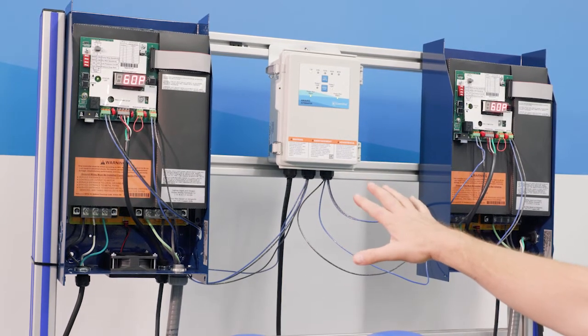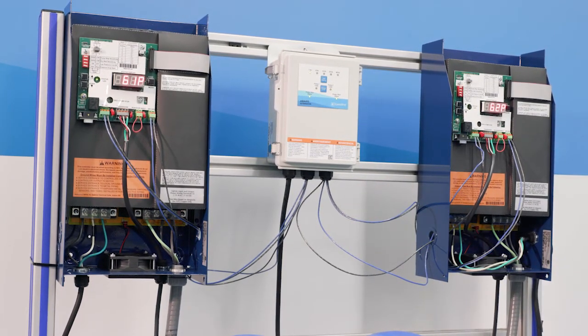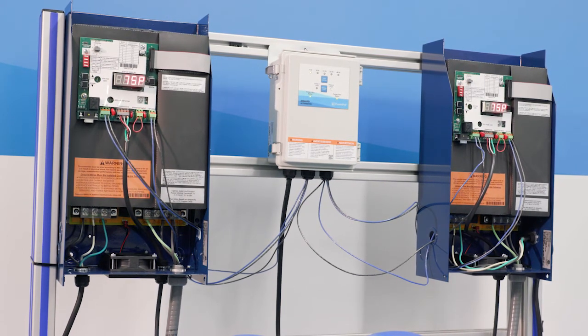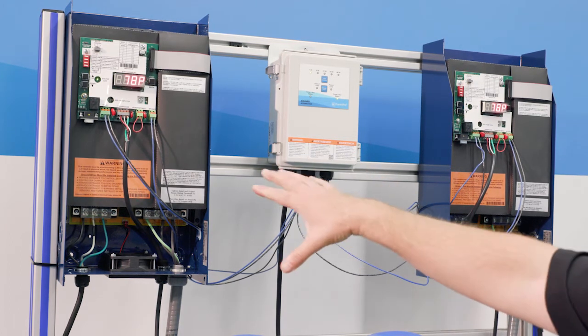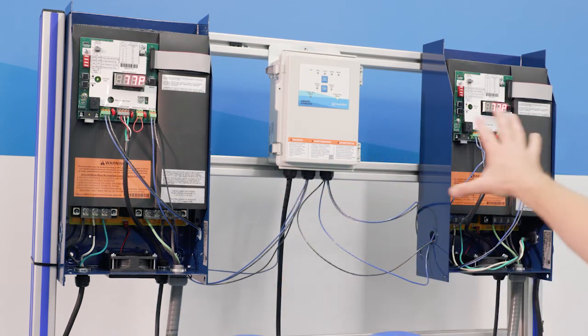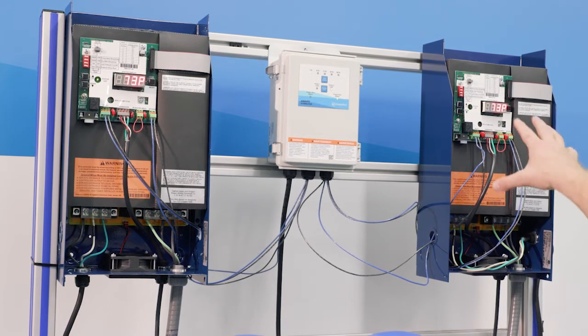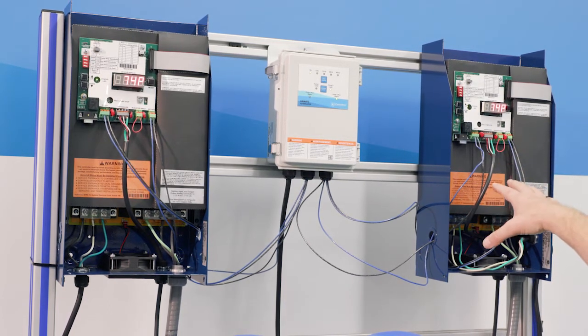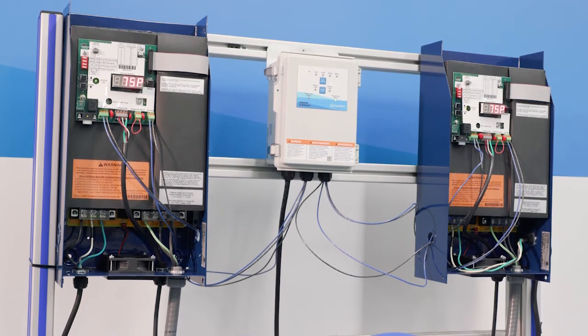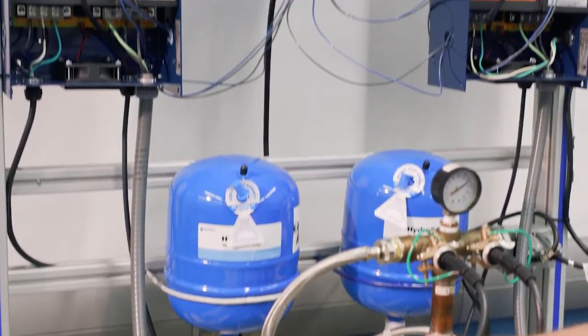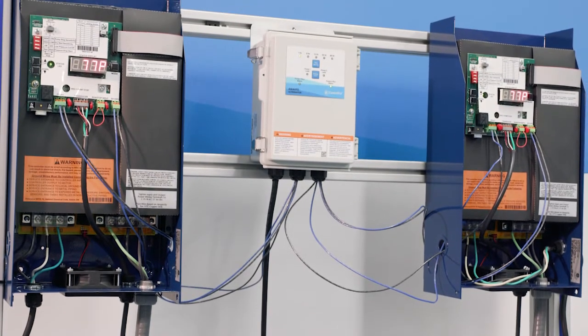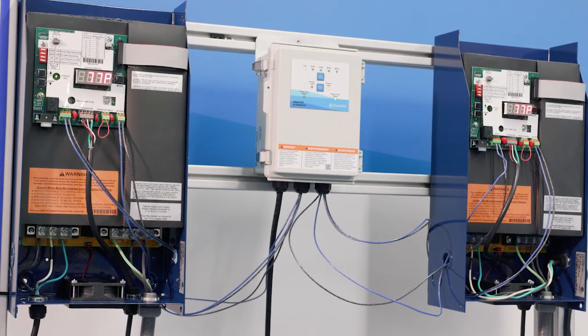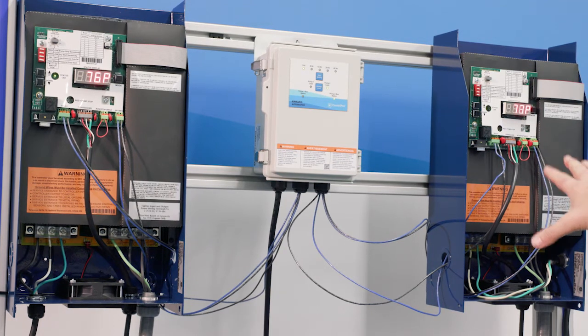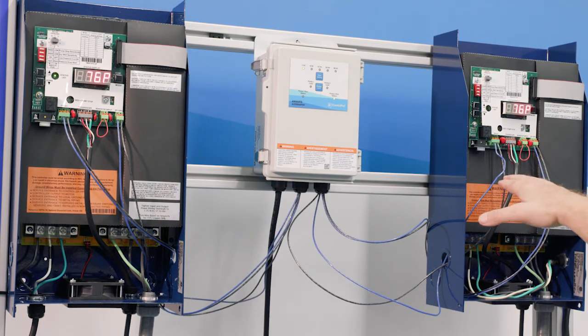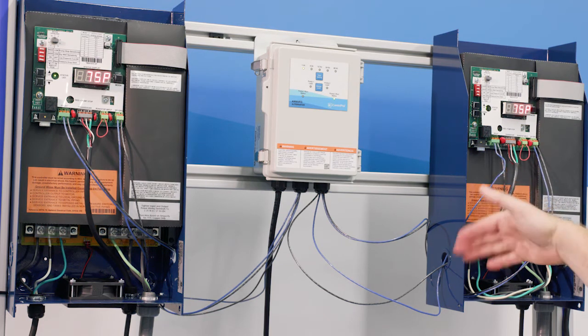So let's close the valve a little bit. We'll get to a point where we don't need the lag system again. We're just running off the lead. Again, it's going back to your lead pressure, SP2, which was 75. All right, so now we're going to close the valve so there's no demand. Pump 2, which is the lead, is going to turn off when it gets to 30 hertz, or half speed.